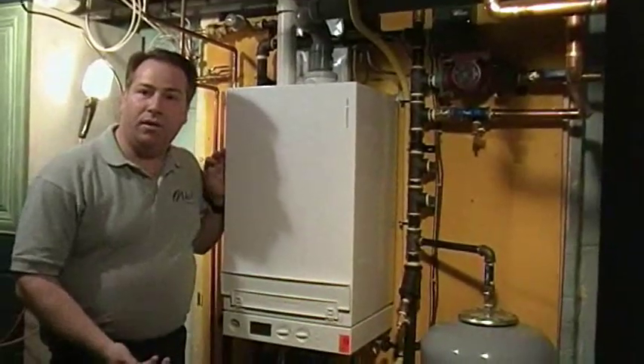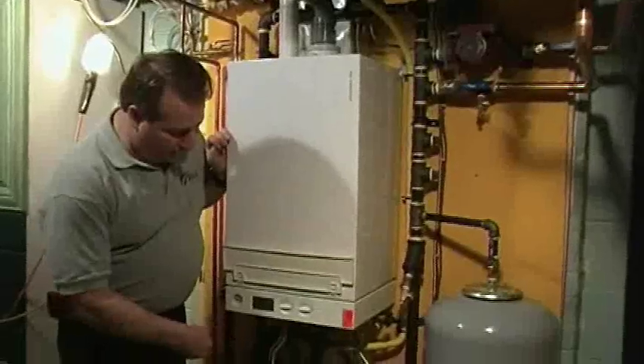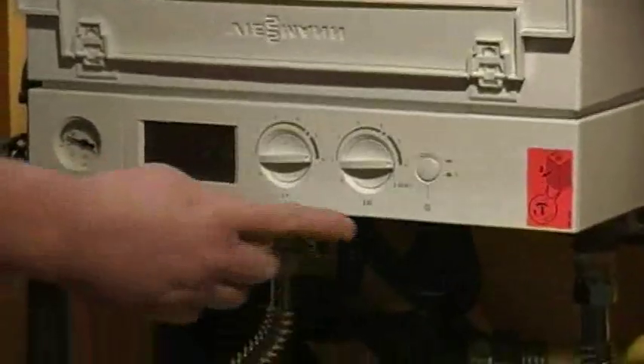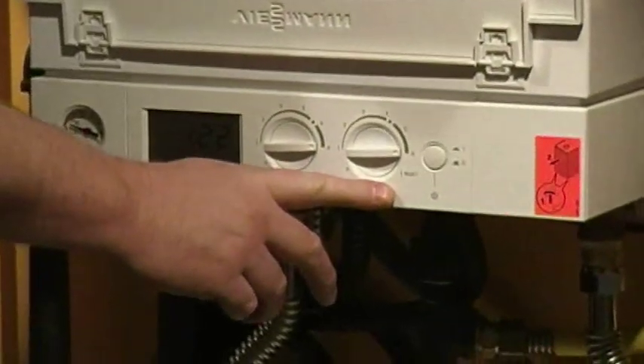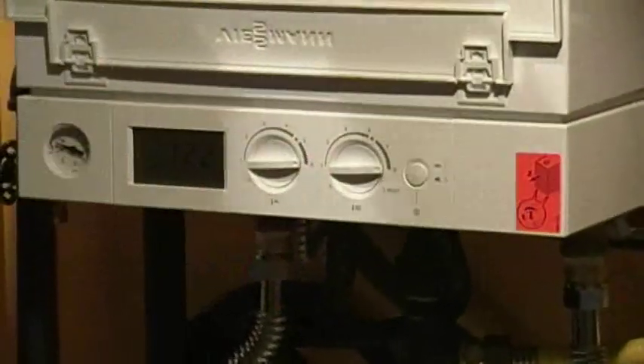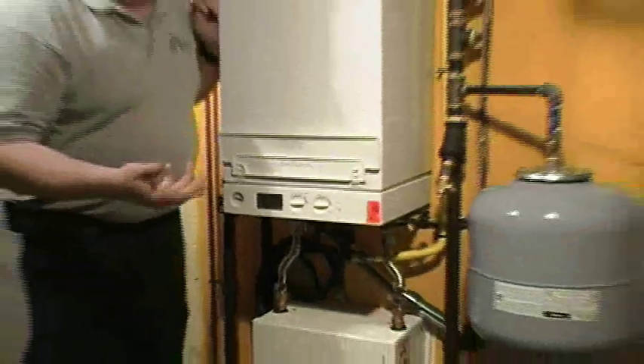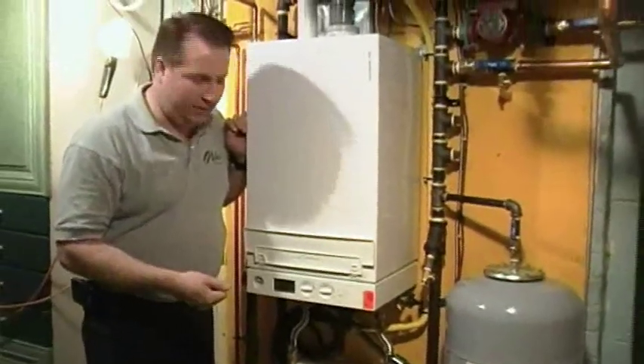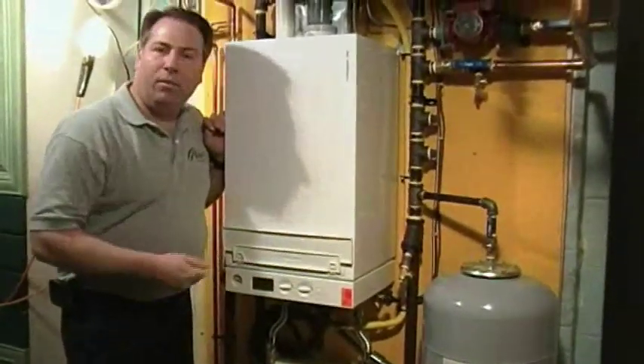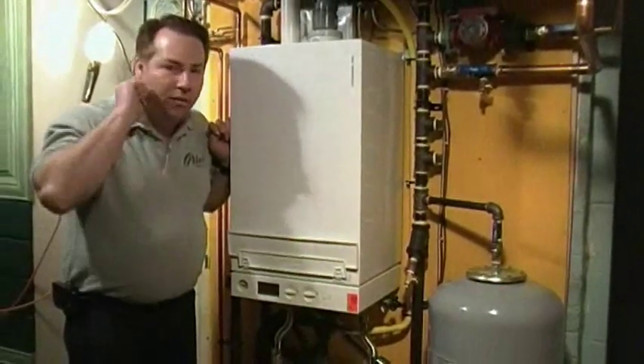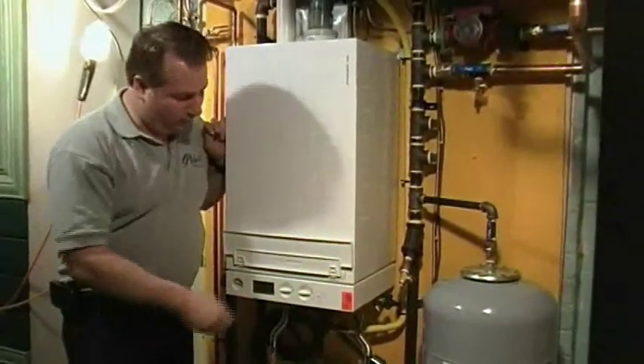There's a few new dials on the system. What we have is the domestic hot water temperature selection. We have the rad temperature selection, and this just adjusts the aggressiveness of the boiler to make either warmer or colder water depending on the outdoor reset. The water temperature works much like a throttle, and the warmer you want the hot water to come out, the more you turn your water temperature up on the dial.